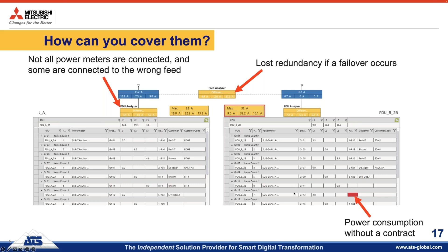So these are two bus bars, the A and the B bus bars, with three feeds. What we do, for example, is look at all the separate installed PDUs on the bus bar, add them all up, and compare them with the main power meter. So the difference should be 0, and if not 0, there's an error. The same is true on the right bottom part. You can see a red rectangle - that means there is no customer using this rack, or at least no customer contract attached to this rack, but he's still using power.